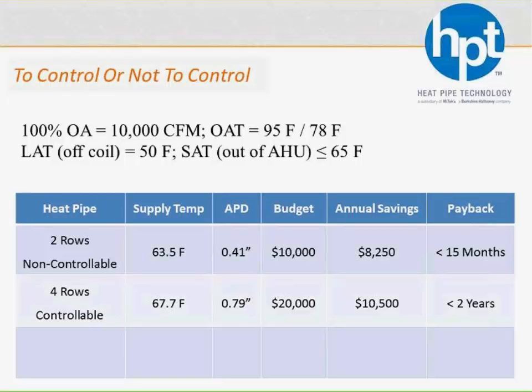Look at the valves as a way to optimize the heat pipe, oversize it, so to speak, because again, you don't spend most of your time at 95 degrees or that peak day. You spend most of your time less than that. So why size your heat pipe so that it's doing its best savings on the day you spend the fewest amount of time? Let's size it for the days you're going to spend the most amount of your time and really capture those savings. And we can take it a step further.